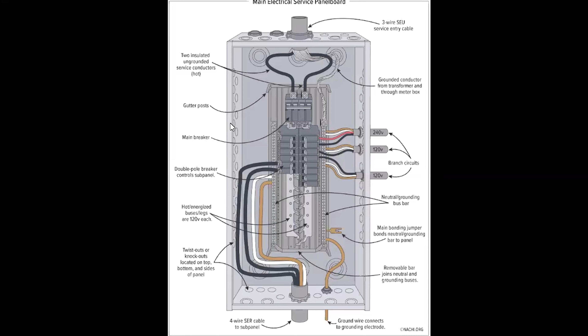You may have noticed it says each bus bar on the hot energized side is 120 volts. Today's terminology usually says 110, but it can go up to 120, so your 220 is actually 240. There's a lot of extra voltage that can be in a panel, so be cautious when taking these apart.